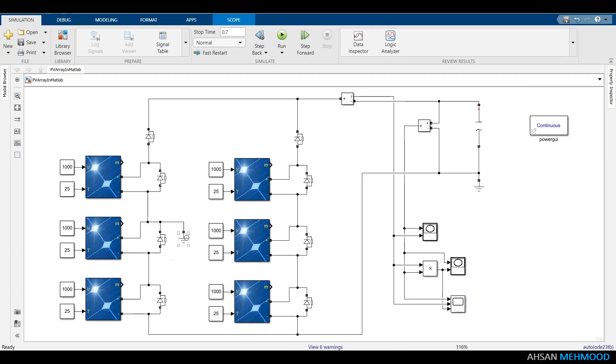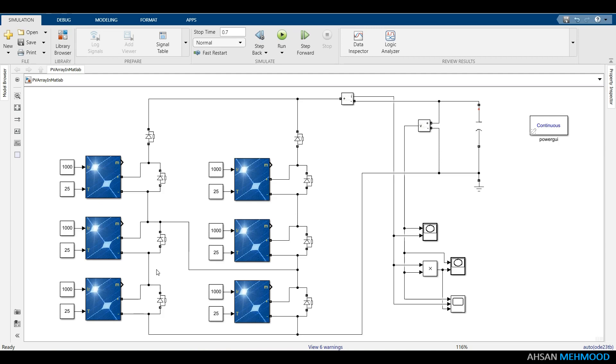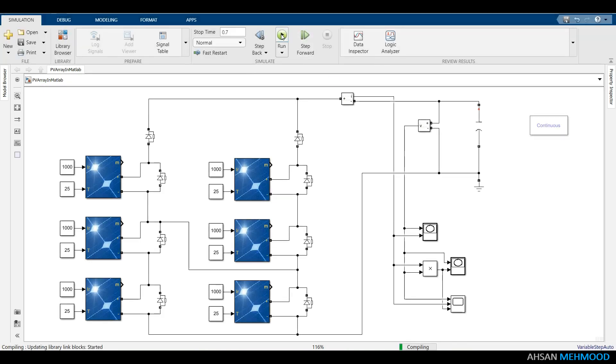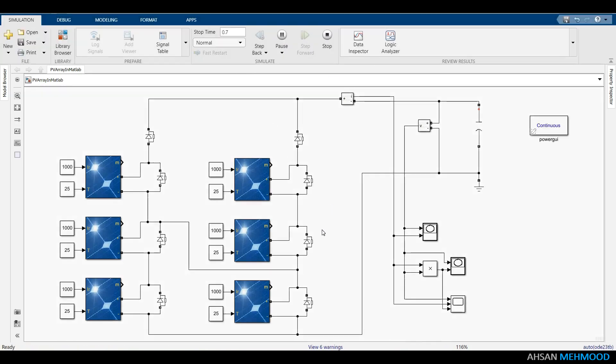To create line-to-line fault between strings with 33% mismatch, connect positive terminal of second module of string 1 to the positive terminal of third module of string 2. You can alternatively do the opposite, that is connect positive terminal of second module of string 2 to the positive terminal of third module of string 1. Both are equivalent faults. Here 33% mismatch means only one module out of three modules in a string is under fault condition.